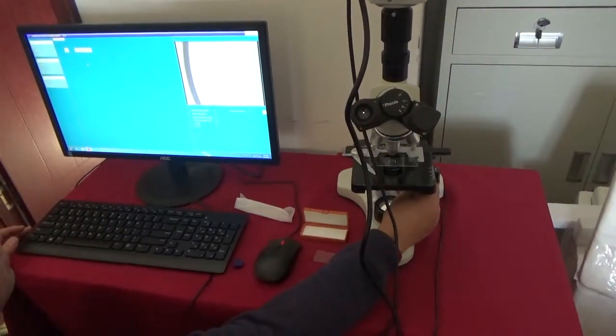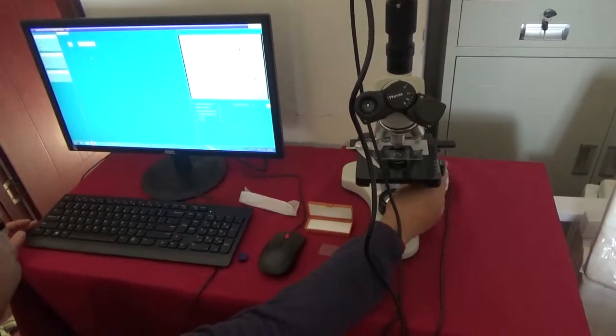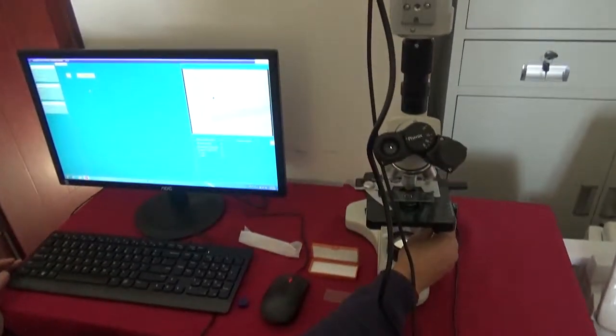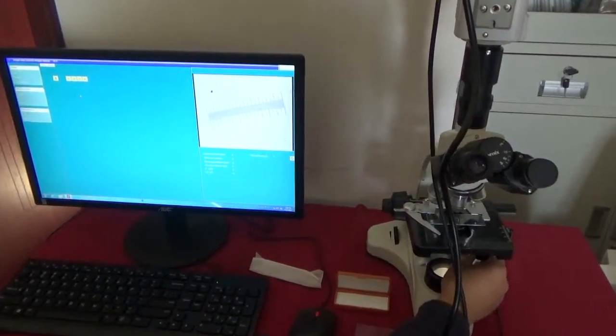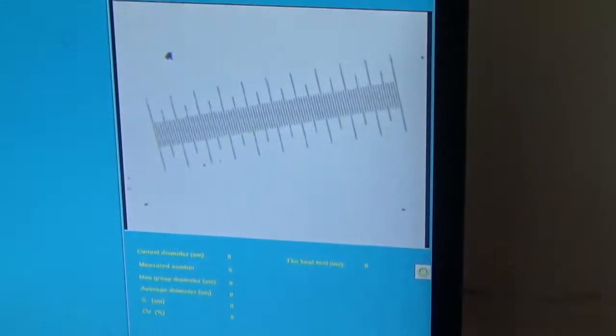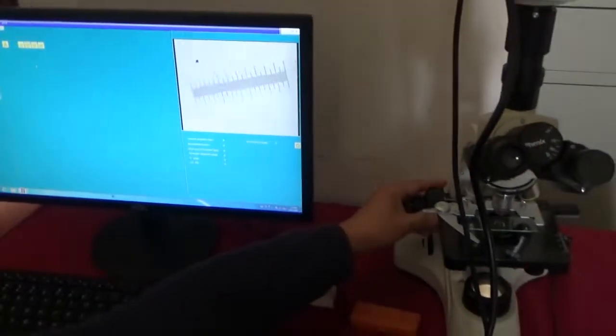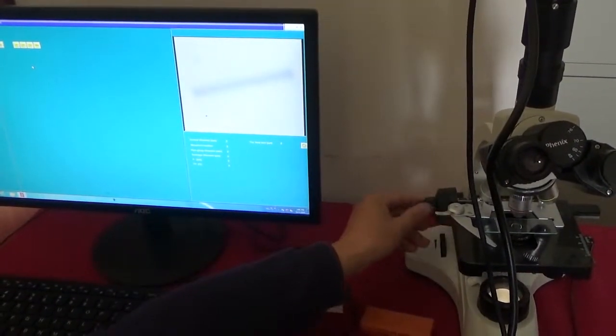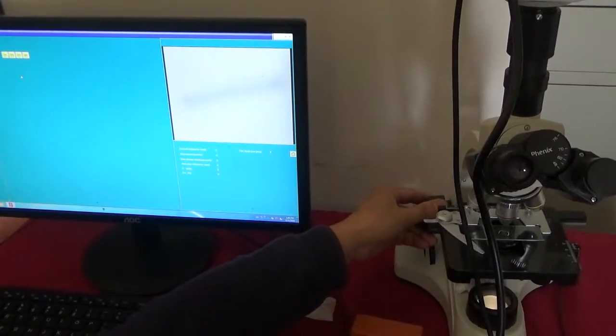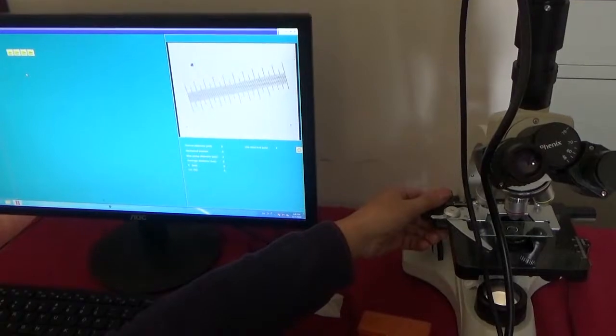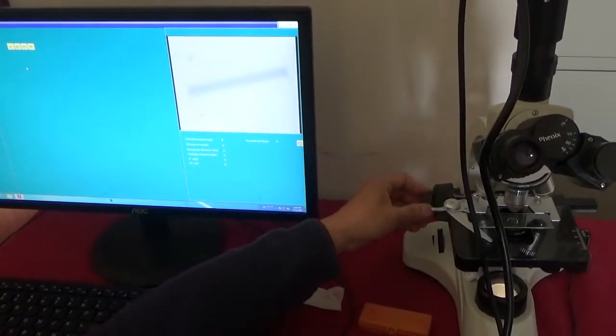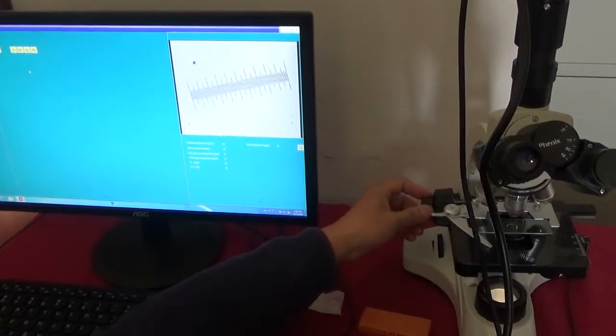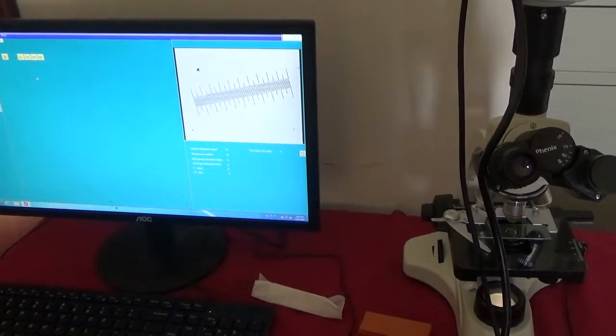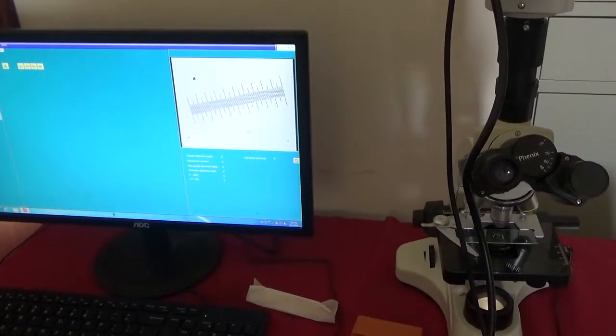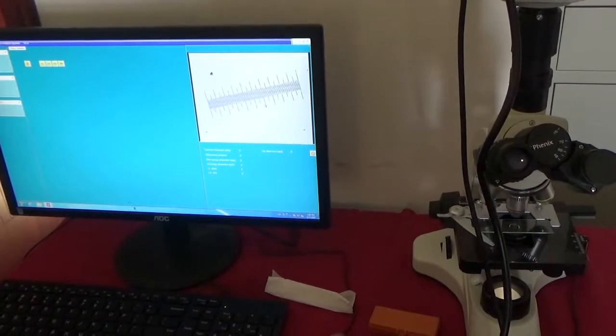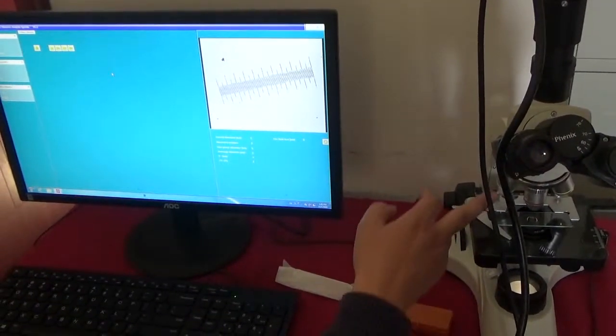Adjust the stage to get a clear picture on the test software. If you can't see a clear picture, you can turn these 2 buttons to adjust the focus of the microscope. This is the coarse adjustment. This is the fine adjustment.